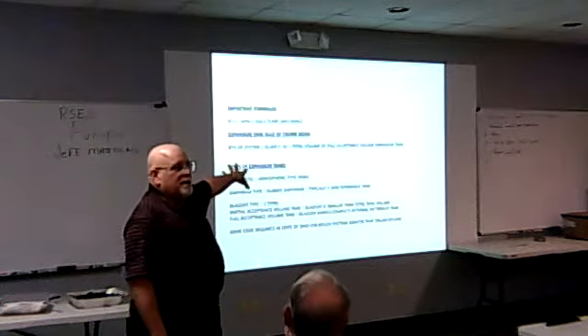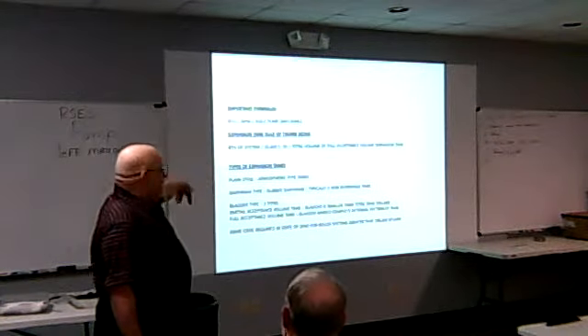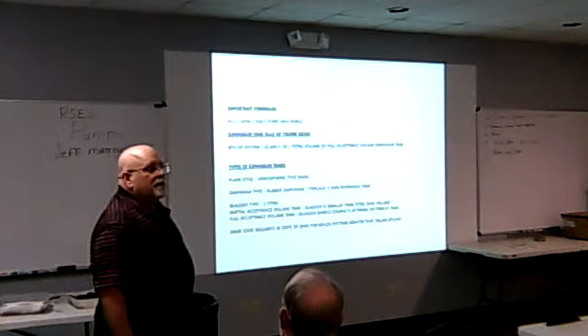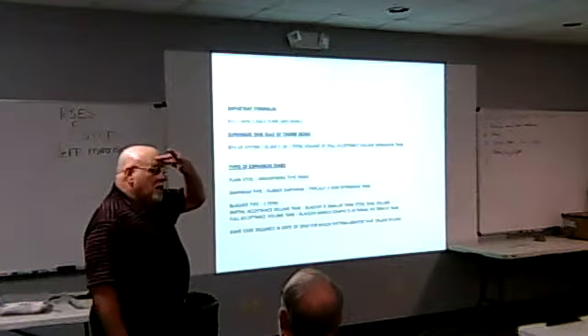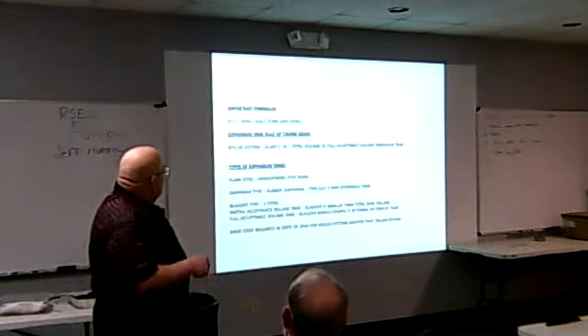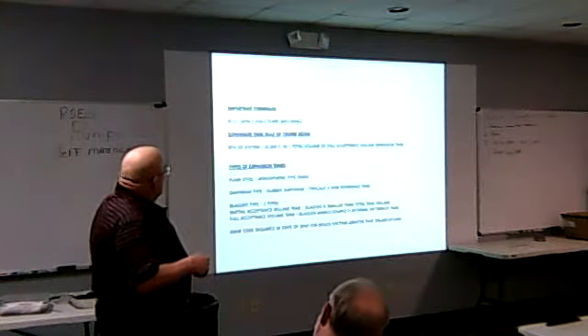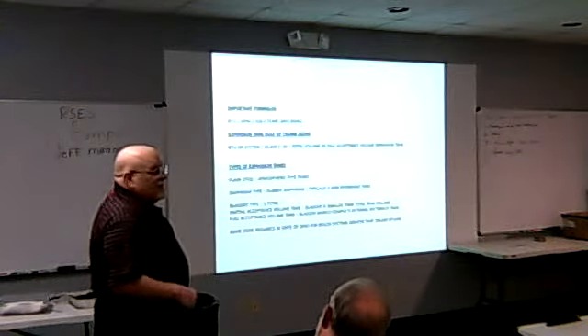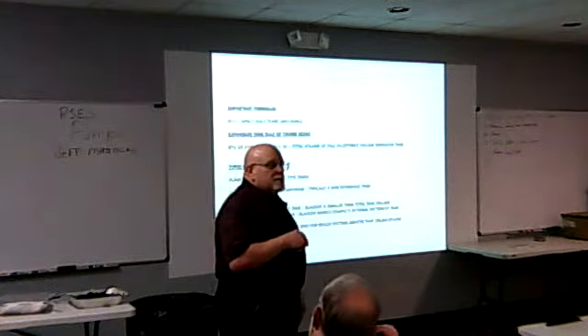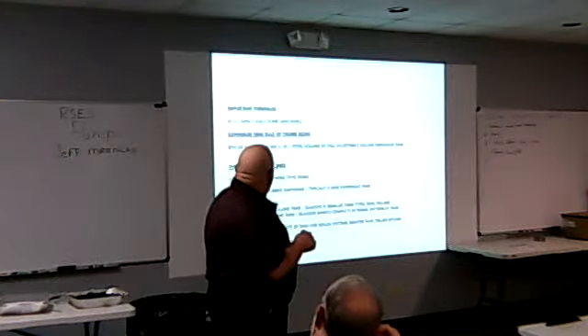If you don't know what your system volume is, you can guess at it by taking your BTUs divided by 50,000 times 5.5, assuming that somebody sized the boiler. I understand that if you have an existing system working for 20 years with a plain steel tank in the system instead of a bladder, get rid of the 5.5 and just divide by 15,000. That will tell me the full acceptance of my bladder tank also. It just happens to all work out perfectly.